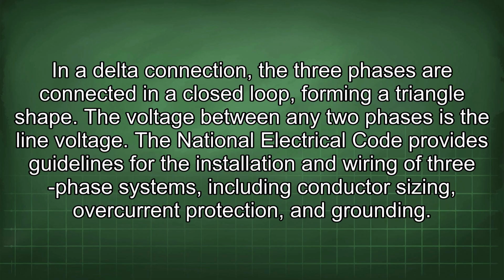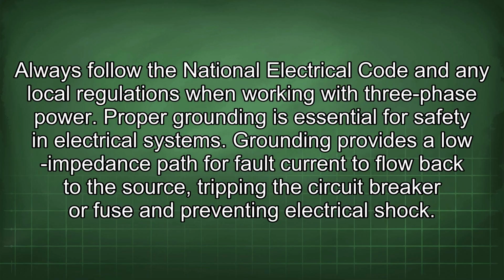The National Electrical Code provides guidelines for the installation and wiring of three-phase systems, including conductor sizing, overcurrent protection, and grounding. Always follow the National Electrical Code and any local regulations when working with three-phase power. Proper grounding is essential for safety in electrical systems. Grounding provides a low impedance path for fault current to flow back to the source, tripping the circuit breaker or fuse and preventing electrical shock.